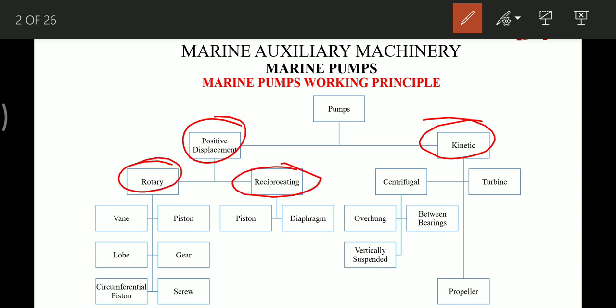Rotary pumps are of many types. First are vane pumps, which are used in the priming unit for centrifugal pumps. Then lobe pumps, which are used for the transfer of sludge. Then we have circumferential piston pumps.